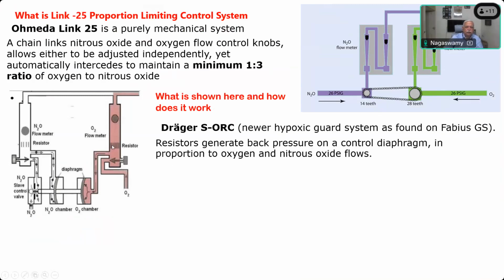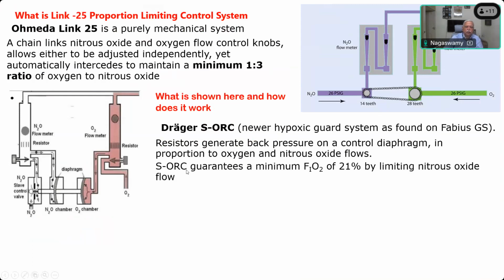There are resistors in the flow meter which generate back pressure on the control diaphragm. This is the control diaphragm for oxygen and nitrous oxide, in proportion to oxygen and nitrous oxide flow. So SORC guarantees a minimum FiO2 of 21% by limiting nitrous oxide flow.